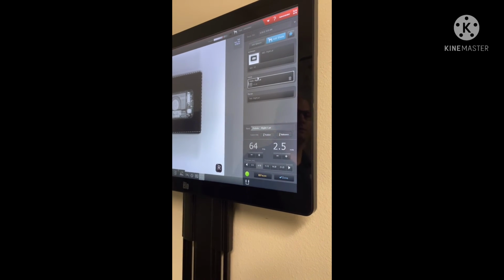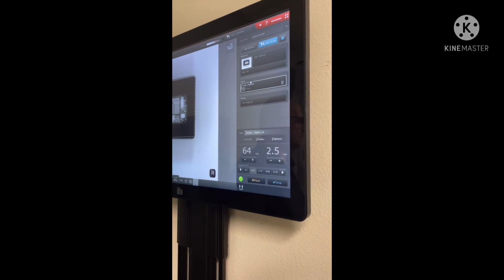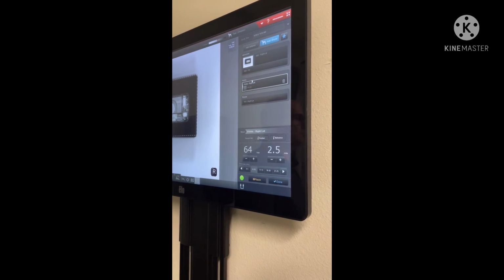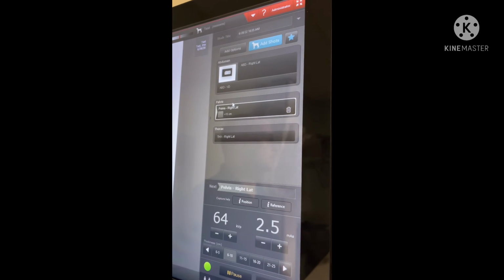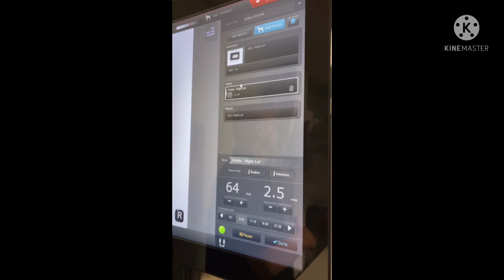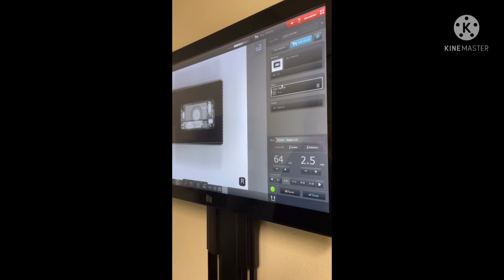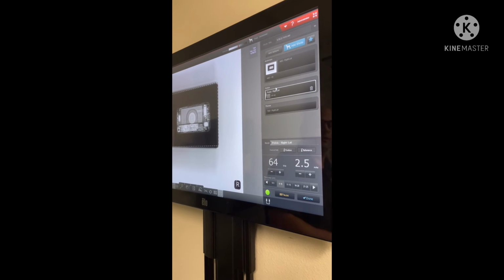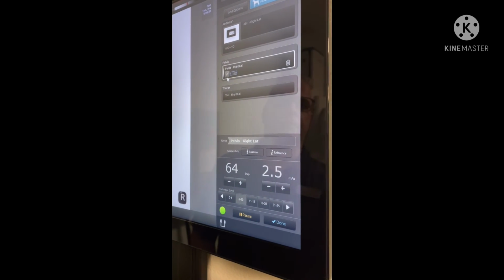Any one of those kinds of shots, it's going to ask you, basically, is the measurement greater than a certain value? So sometimes it's 10 centimeters. In this case, if it's pelvis, it's asking, is it thicker than 15 centimeters? You don't have to do an additional measurement. It's the same measurement that you're doing for your technique. It's just you're taking that number, and if it's greater than 15 centimeters, you want to check that box.